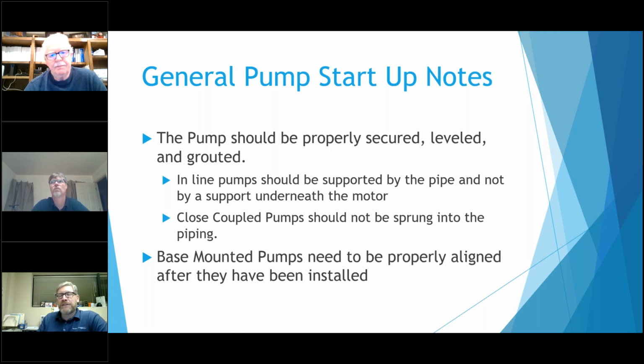B&G, I think it was about 2015, redesigned their new E-Series pumps. Some of this redesign was to get more efficiency out of the pumps. So there are a lot tighter tolerances on these, and they also changed from bronze material on the impeller to stainless steel. Where that's important in alignment is that these tolerances are so tight anymore that you can turn a pump on, and next thing you know, it's noisy, it's loud, you hear the throbbing noise. When you had that brass impeller with these bigger tolerances, you would say, well, I'll just let it run in, and eventually the noise would go away. But with the new pumps, that stainless is a lot tougher than brass, so it doesn't really run in, but it's an indicator just by even hearing that the pump may not have been aligned.